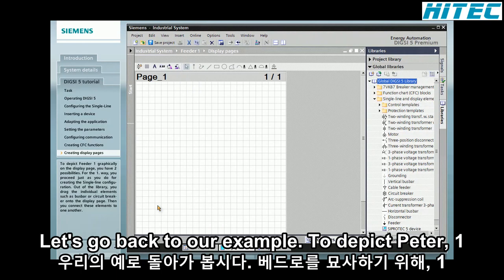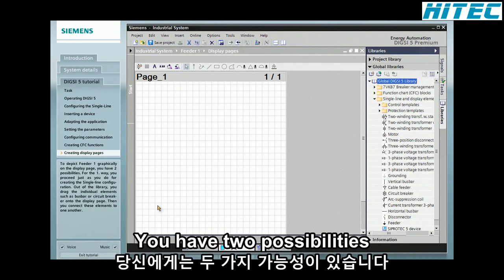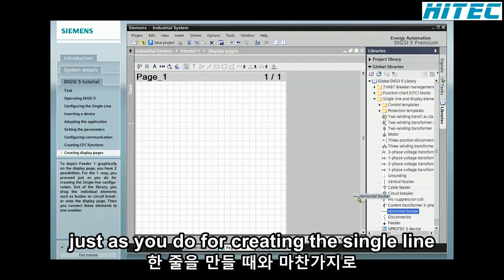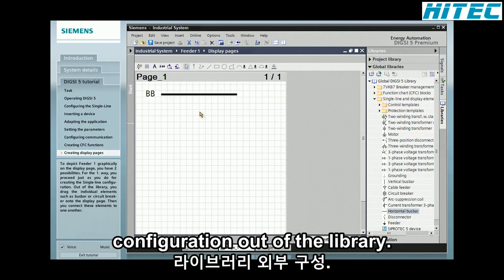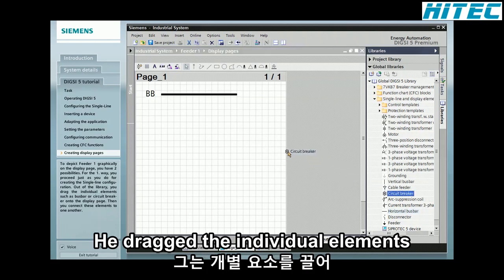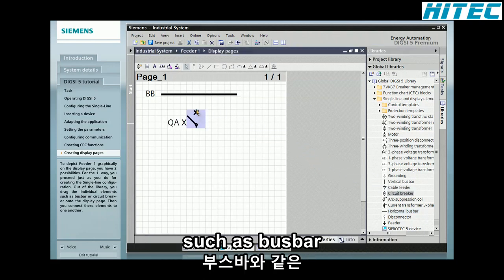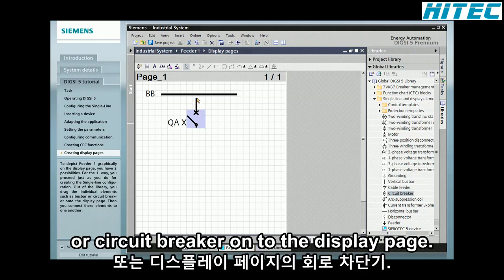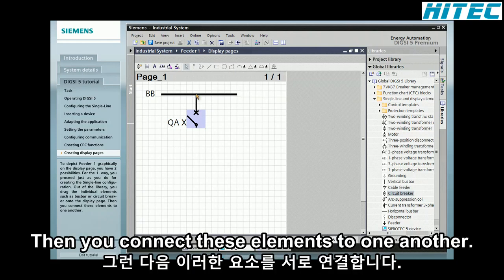To depict feeder 1 graphically on the display page, you have two possibilities. For the first way, you proceed just as you do for creating the single-line configuration. Out of the library, you drag the individual elements such as busbar or circuit breaker onto the display page. Then you connect these elements to one another.